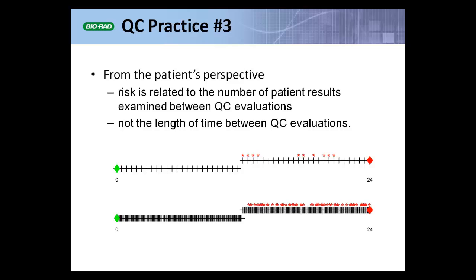So patient risk isn't related to the 24 hours — it's related to the number of patients tested between those two QC events. Go ahead and schedule by time, but be aware of the average number of analyte examinations you're doing between QC events. It's going to differ for every analyte, but risk, from the patient's perspective, is related to the number of analyte examinations between QC events.